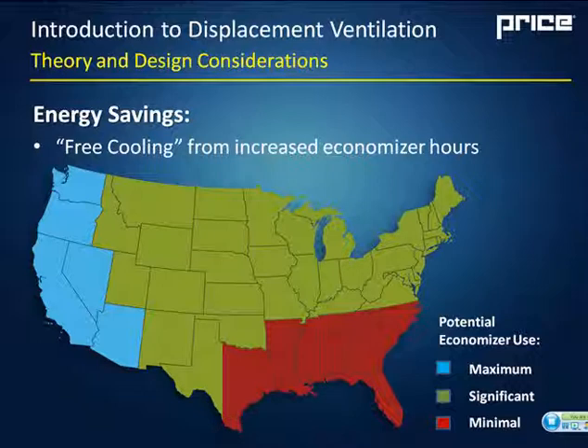Moving across the U.S., the rest of the U.S. is basically in the area that we consider significant. So there's probably significant potential in the shoulder seasons and portions of the year where they can still be pulling in a significant amount of air, or using the economizer for a significant amount of hours. Again, as I mentioned, in the southeast where the humidity is very high and the cooling load is very high as well, the potential for free cooling is pretty minimal, simply because the dew point temperature is just much warmer than it's comfortable to supply.